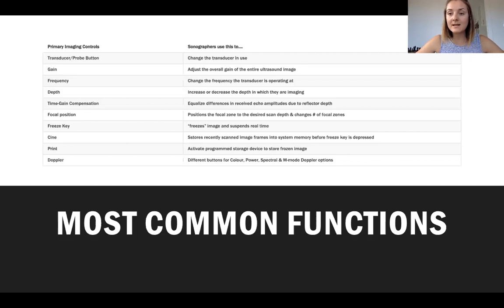The other thing that we can do is we can turn down our gain and we can turn it down so almost everything looks really dark or black or anechoic or even hypoechoic on our screen. Obviously, there is a balance as to what kind of gain we want to see because you do want to be able to tell the difference between the different echo textures in our organs. The frequency button is what allows us to change or toggle between different frequencies. This is a result of our actual transducers being broad bandwidth transducers, which means they don't operate just at one frequency.